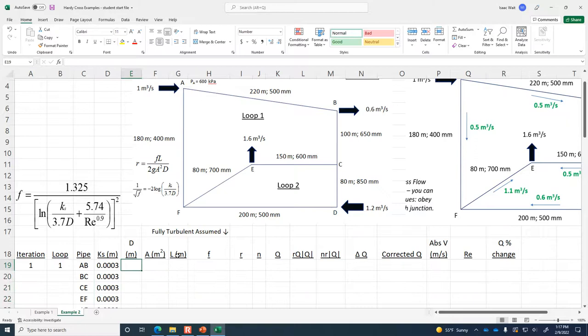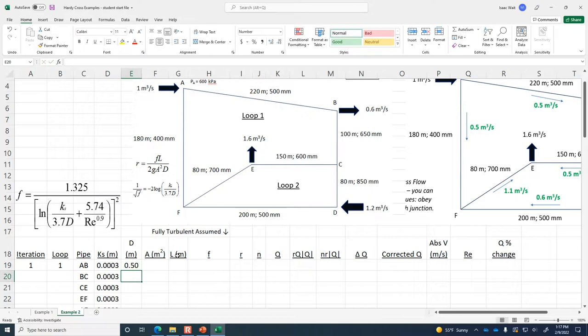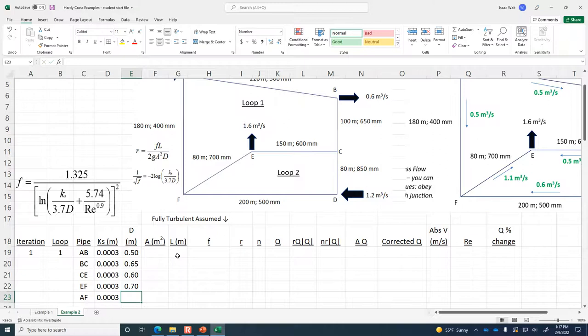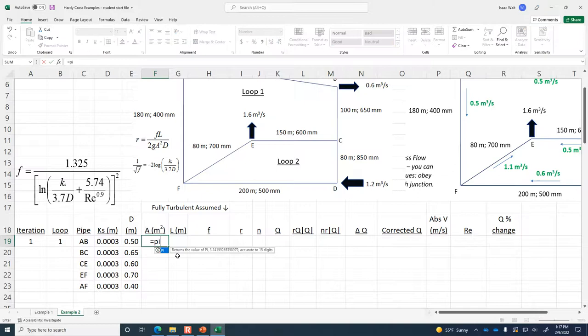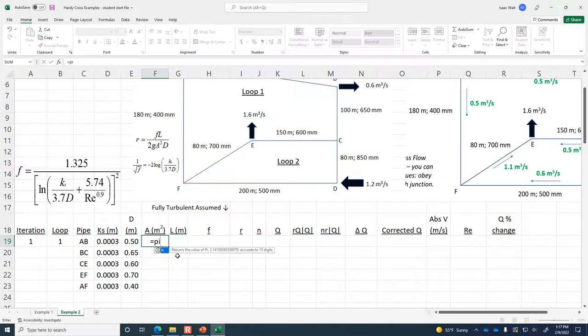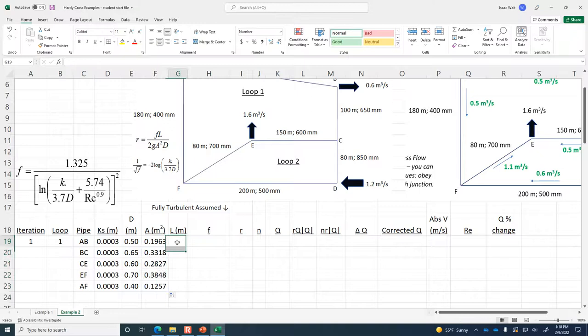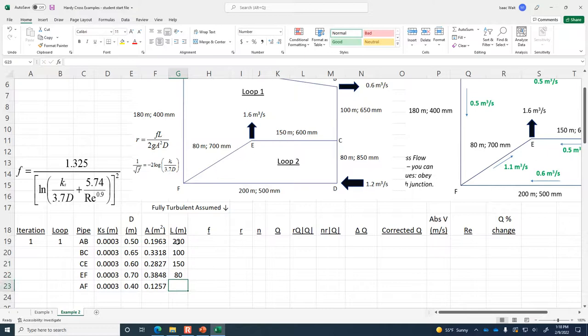The diameters: AB is 0.5 m, BC is 0.65 m, CE is 0.6 m, EF is 0.7 m, and AF is 0.4 m. The cross-sectional area is pi times D squared divided by 4, and we drag that down for each pipe diameter. Then we put in the length of each pipe: 220 m, 100 m, 150 m, 80 m, and 180 m.